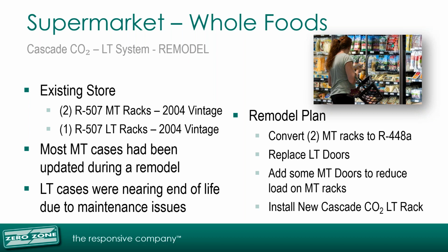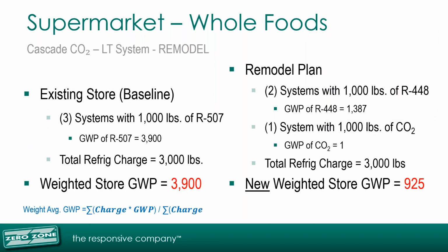The remodel plan was to convert the 2 medium temp racks to R448A, replace the low temperature doors, and add a new low temperature CO2 cascade system. Doors were added to the medium temp cases to reduce the overall medium temp load and to make room for the low temperature cascade system. Please note the refrigerant charges on the slide are only an estimate.